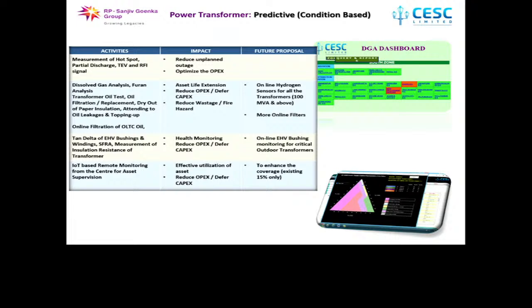We carry out DGA also, and that data is manually fed into the system, and we have a dashboard through which we can see the condition of the oil. Based on that, we carry out oil filtration, and if we see that filtration is not working, in that case we go for replacement of the entire oil of the transformers. We also have a health indexing system based on this data.